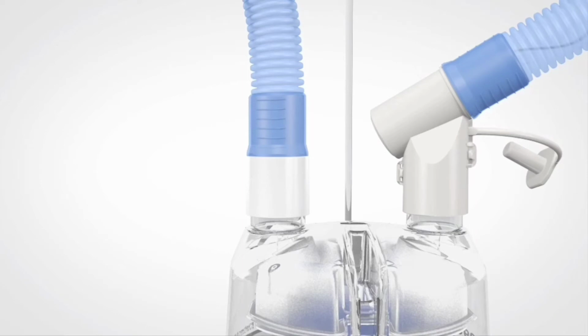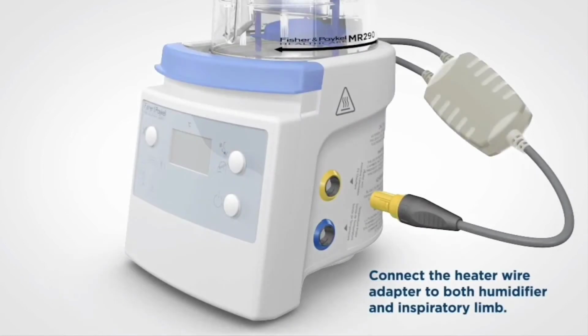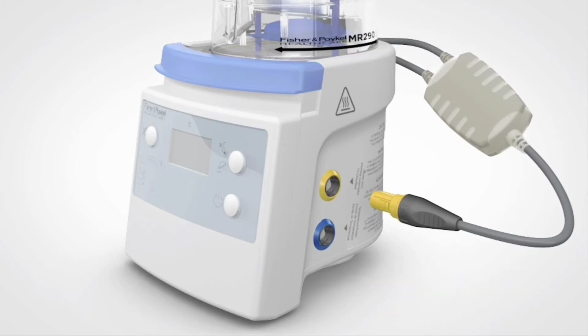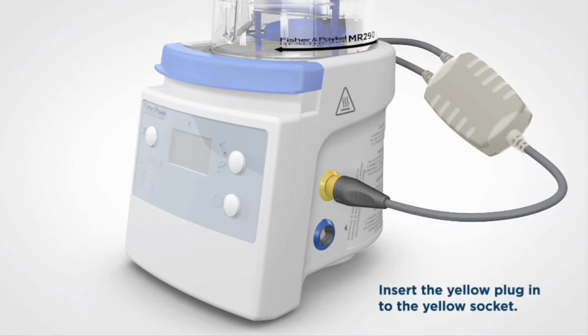Now, let's connect the heater wire and temperature and flow probe adapters. First, let's connect the heater wire adapter. This adapter connects the heated inspiratory limb to the humidifier and provides energy to power the wire in the limb. The humidifier adjusts the energy delivered to the wire to maintain humidity and reduce condensate in the inspiratory limb. Connect the yellow plug to the yellow socket. The socket is both color-coded and keyed to the plug. You may have to turn the plug until it slides in easily. It should click into place.